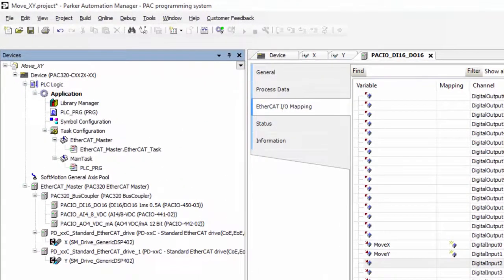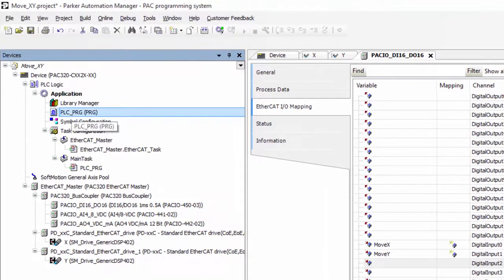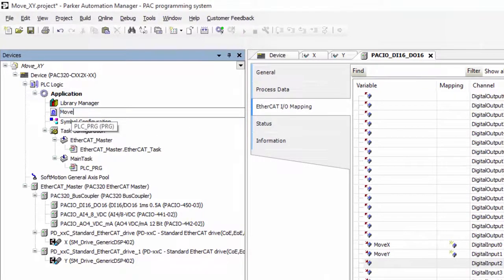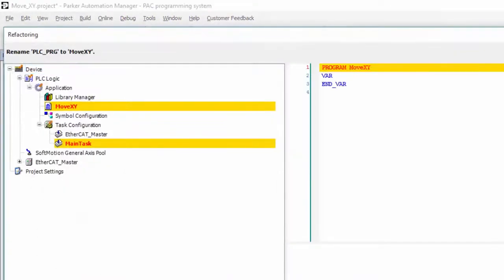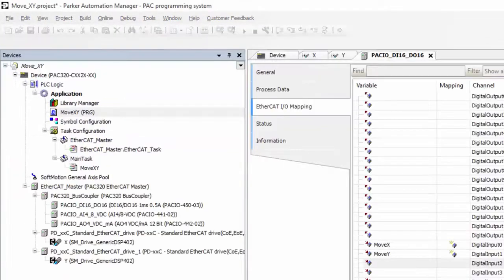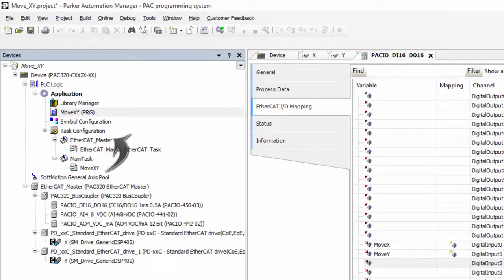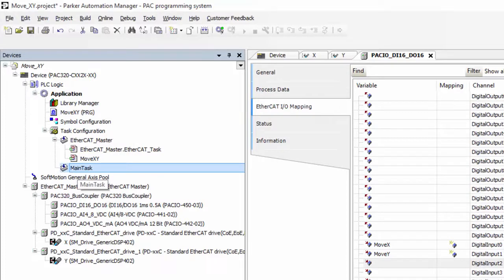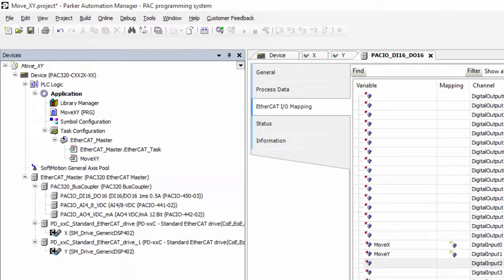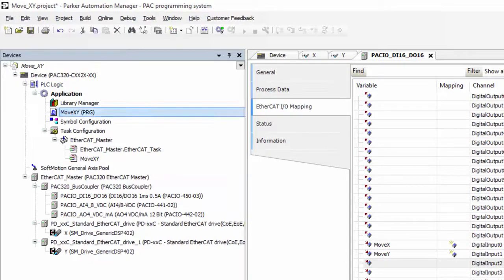I'm going to rename the default program to move X Y, and since it is only going to contain motion commands, I'm going to move it to the EtherCAT underscore master task, where all motion commands should go. We don't need an additional task for this project, so I'm going to go ahead and delete the main task.